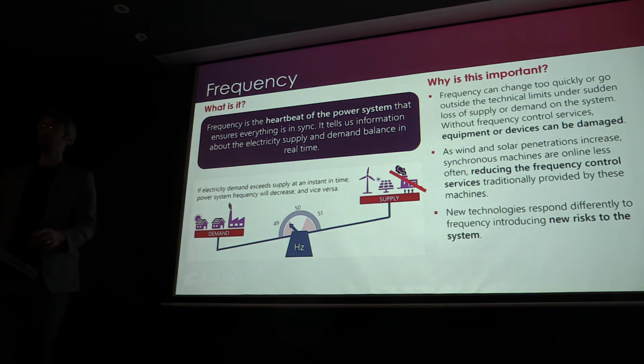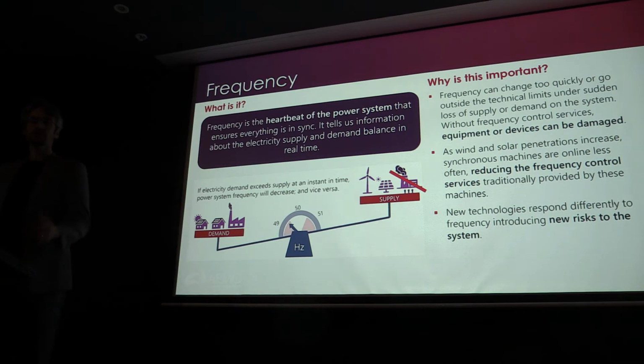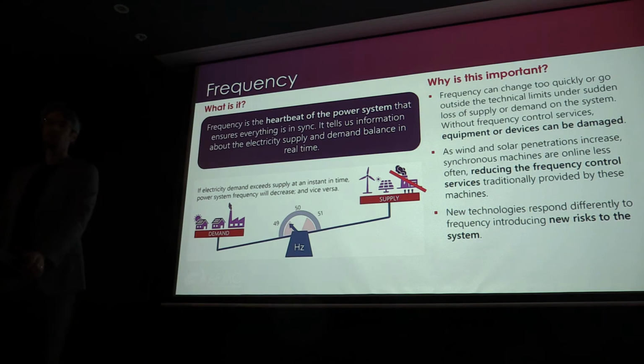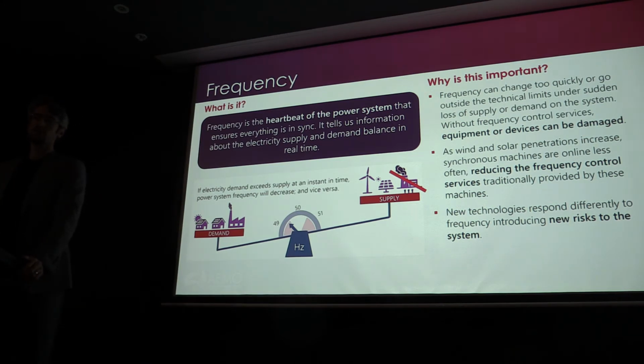A bit of background, stating the obvious: what is frequency? Frequency is the heartbeat of the power system. To me, frequency is like an indicator, a balance between generation and load. When generation is more than load, frequency will be higher than the standard. What is the standard in the SWIS? 50 Hertz. If generation is less than load, frequency will be lower than 50 Hertz. That is a simple fact about frequency. And it is very important to control frequency because equipment and devices connected to electricity might get damaged if frequency goes outside the technical band.